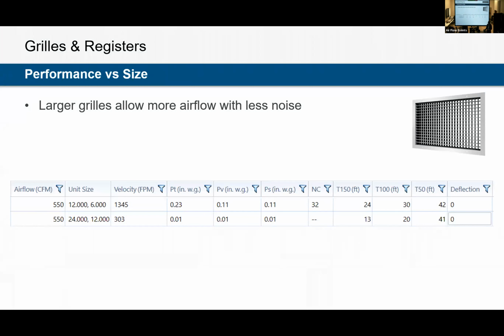Grills and registers. All right, so now we're gonna actually get into some of the selection and performance, why we're actually all here. So we'll start with grills. The key takeaway for grills, and what we're gonna look at here, is pressure drop and sound when we increase size. So we're gonna compare these two different grills here. We're pushing the same airflow. We've got 550 CFM through two different grills. One is 12 by 6 and one is 24 by 12, so double the size. When we keep airflow the same, but double the size of the grill.